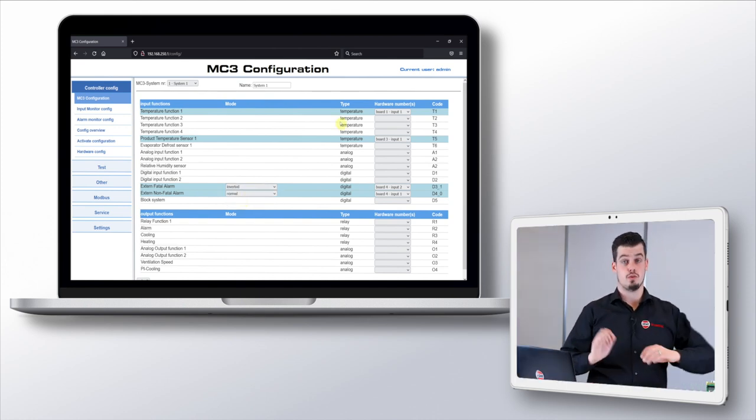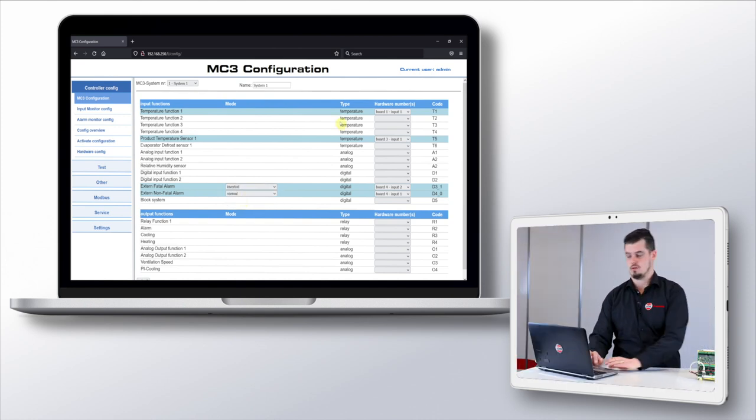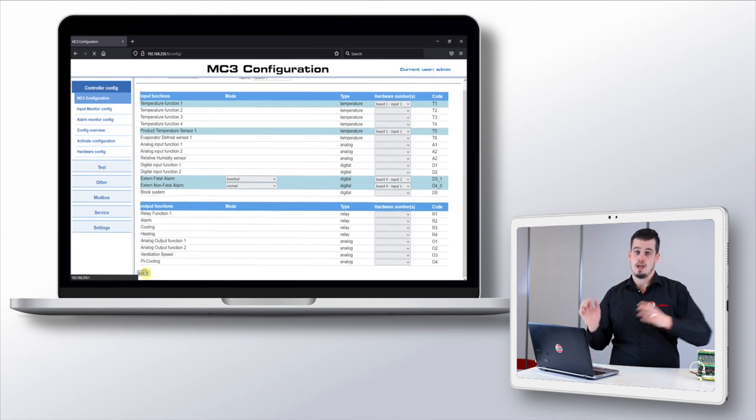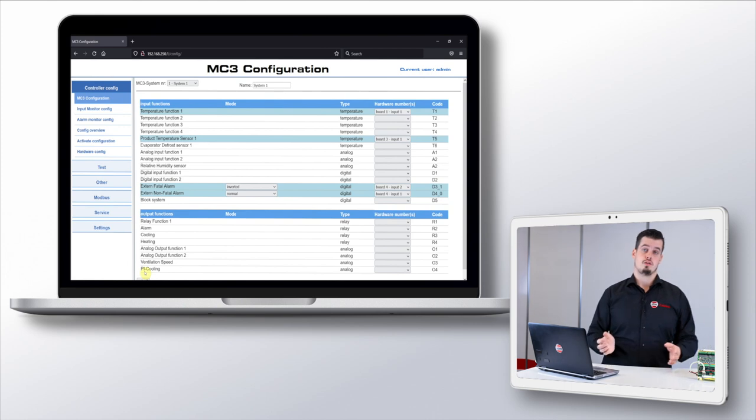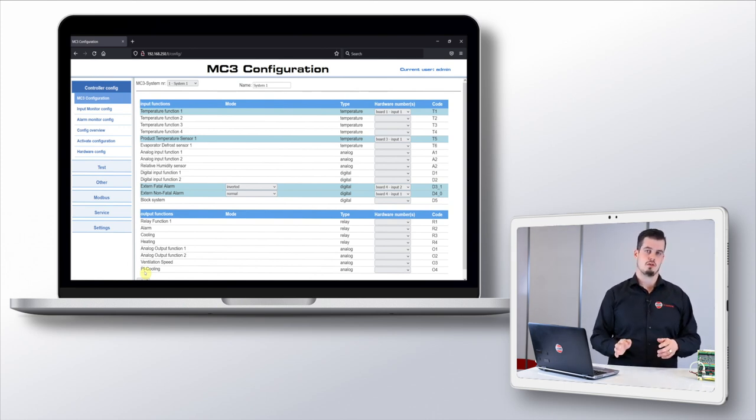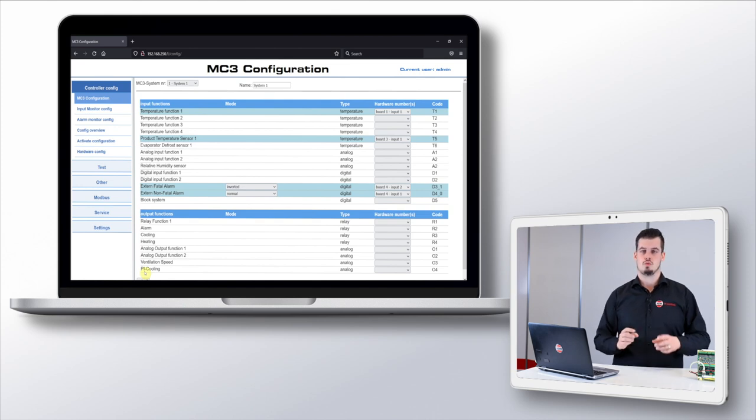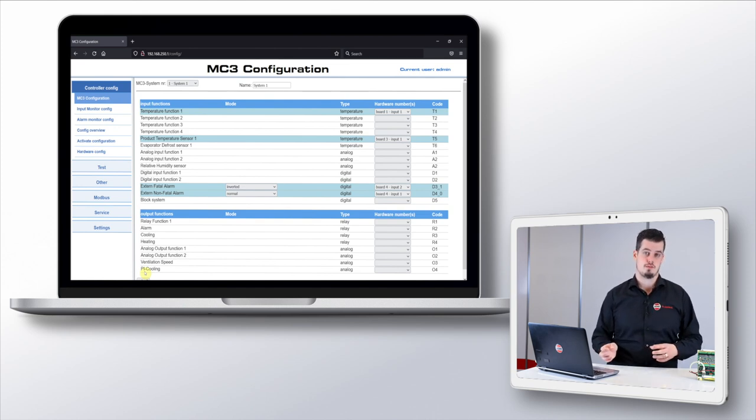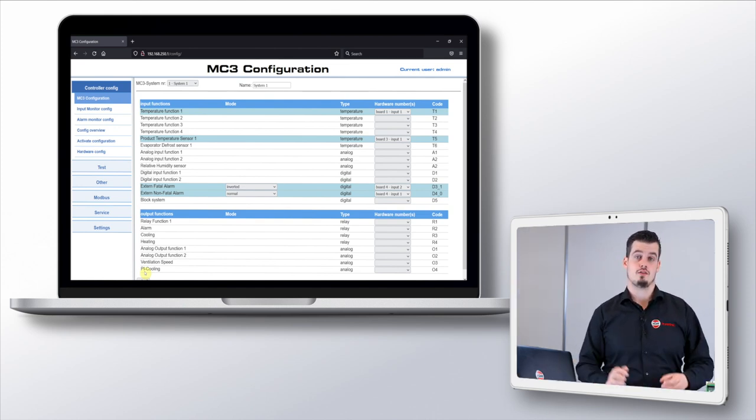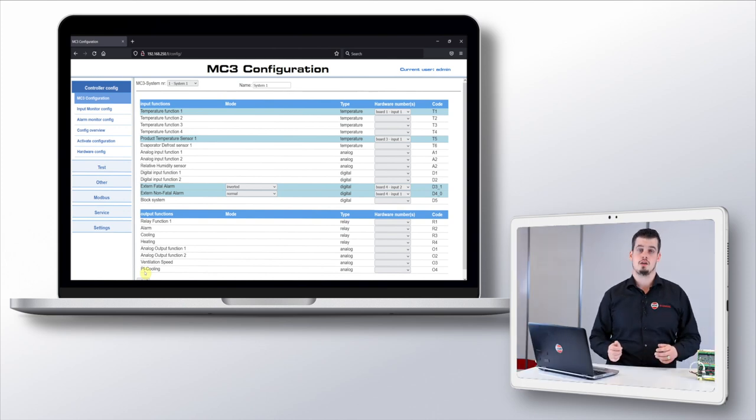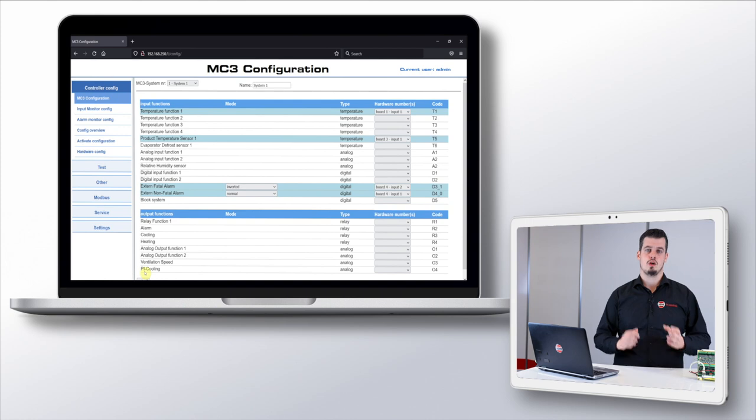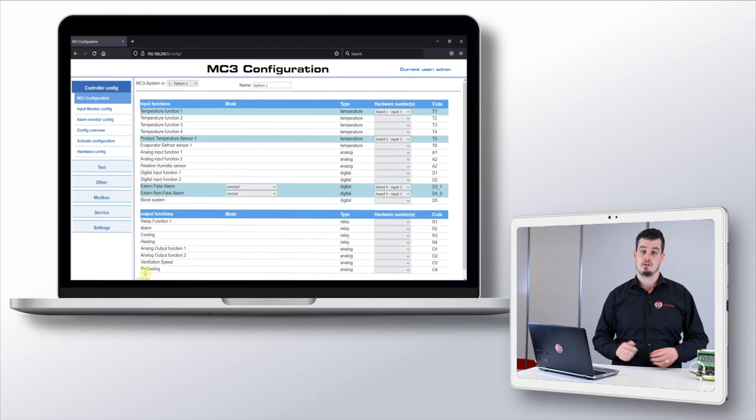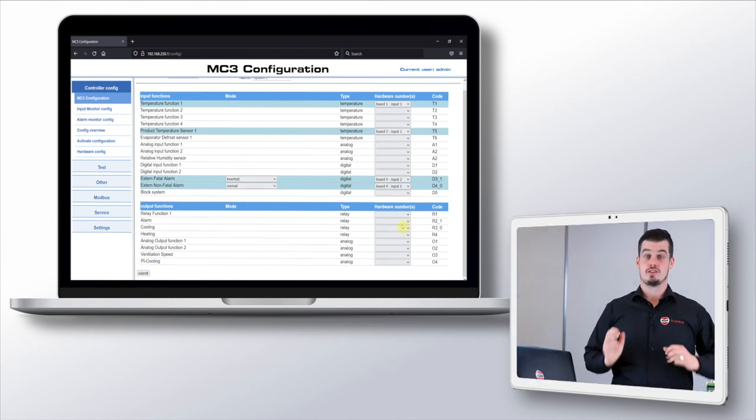Now that we have some inputs configured we press on submit on the bottom of the page, and our new configuration is stored but at this stage not yet used by the controller. We'll go into this in a bit. First we'll go ahead and also configure some outputs for our system. We have our cooling connected to a relay output on board 2 output 1 and an alarm output on board 2 output 4. We want the alarm output to be on or active when there is no alarm and it needs to break or be off when there is an alarm.